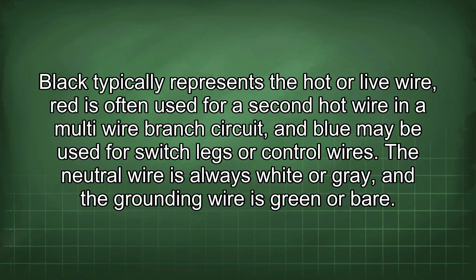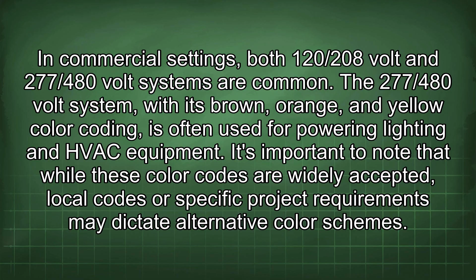In commercial settings, both 120/208 volt and 277/480 volt systems are common. The 277/480 volt system with its brown, orange, and yellow color coding is often used for powering lighting and HVAC equipment. It's important to note that while these color codes are widely accepted, local codes or specific project requirements may dictate alternative color schemes. Always consult the relevant electrical codes and project specifications before commencing any electrical work.